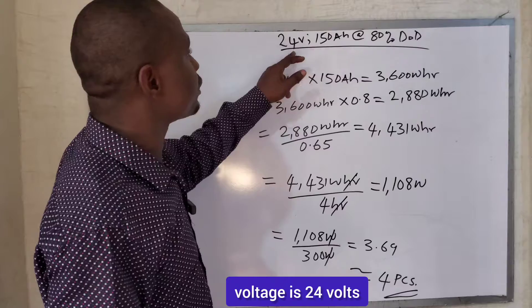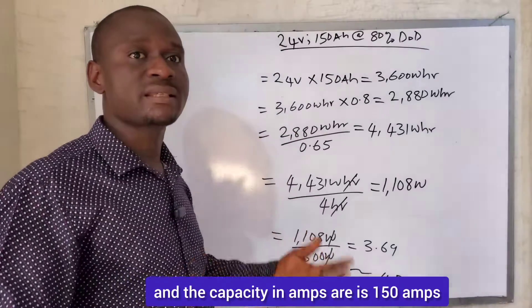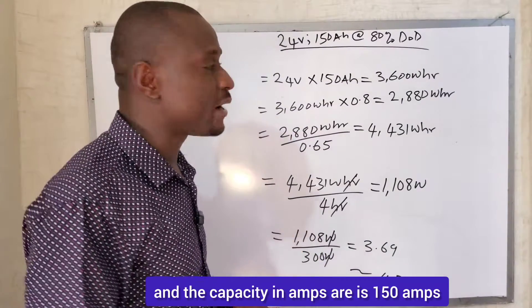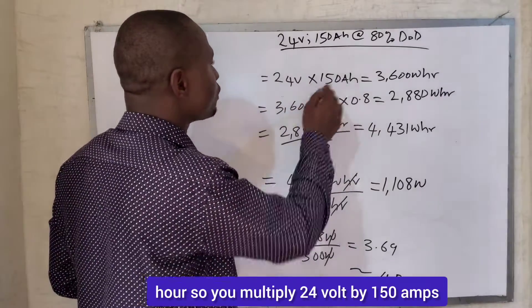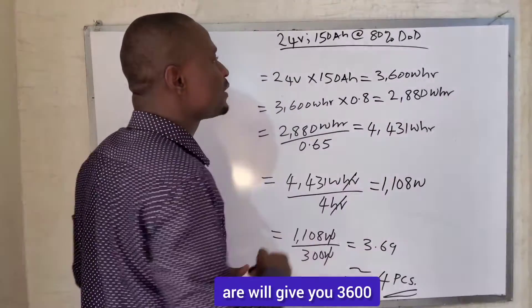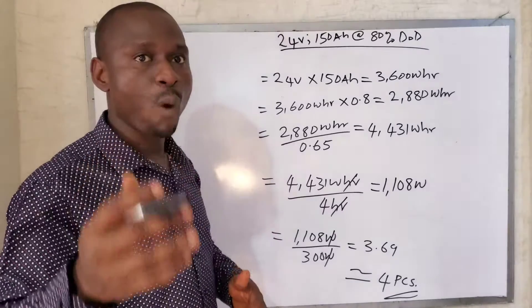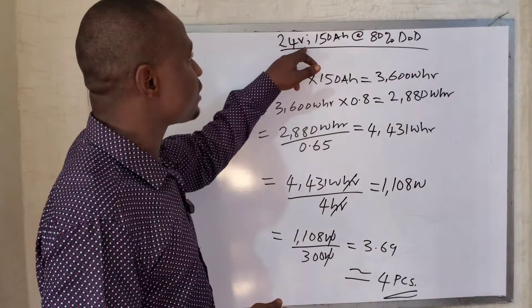The battery bank voltage is 24 volts and the capacity is 150 amp-hours. So you multiply 24 volts by 150 amp-hours, which will give you 3,600 watt-hours. This is the energy that is stored in this battery bank.